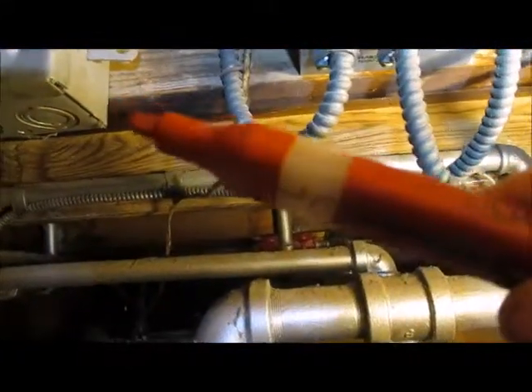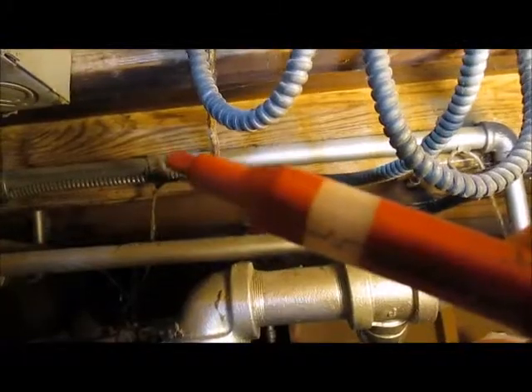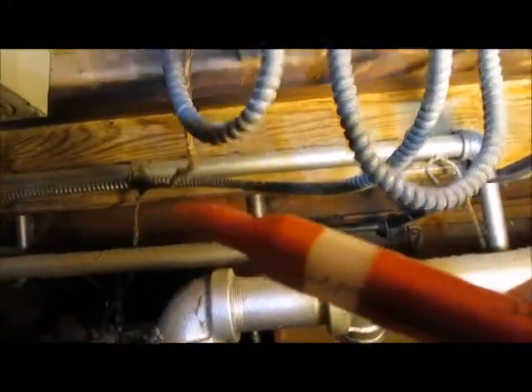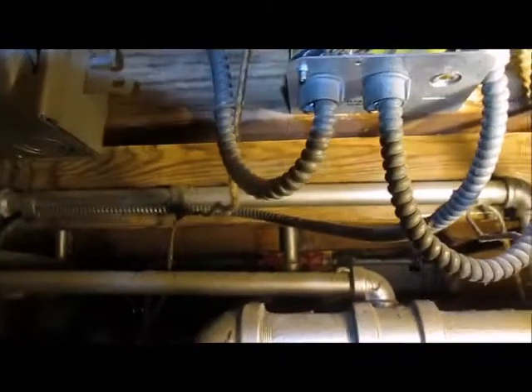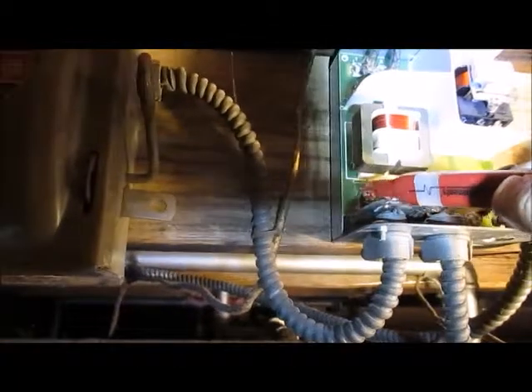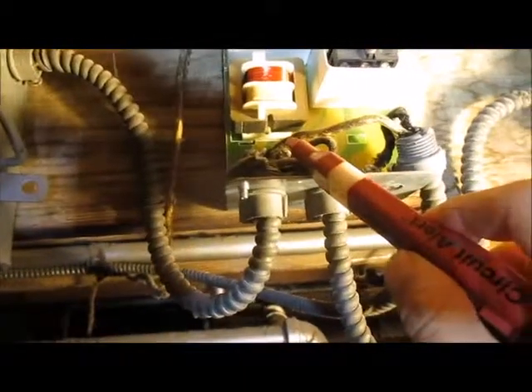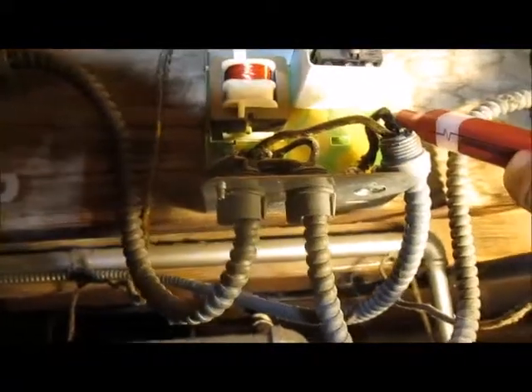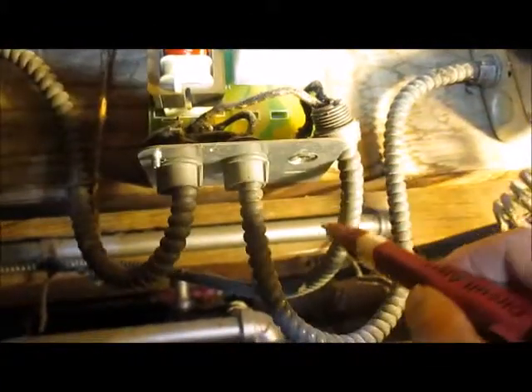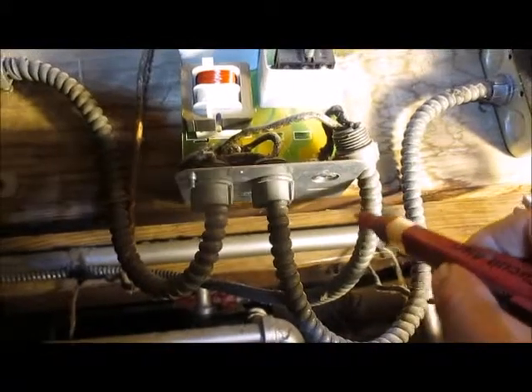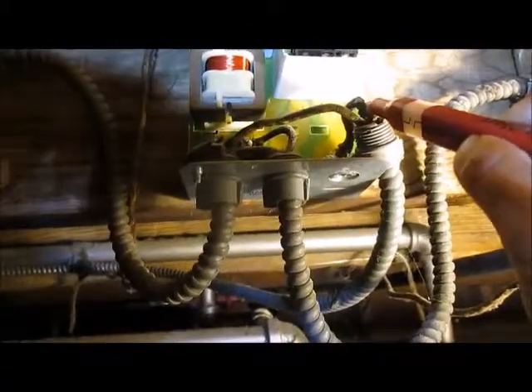Like I was saying, to figure out it wasn't my pump that wasn't working, you go to the wires that lead back to the pump. Right now there's no power going to them at all, but on the rest of the box the tester's going off. So there's power right here, but at the current moment no power is going to the pump wire. That's because the boiler is off right now.